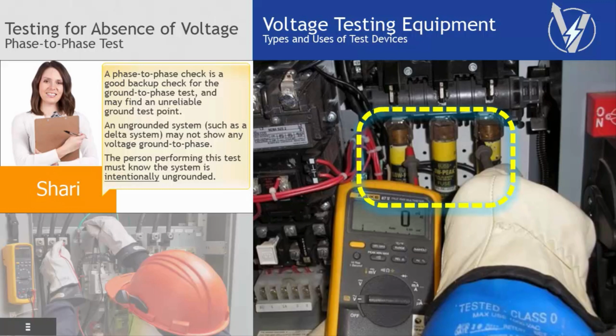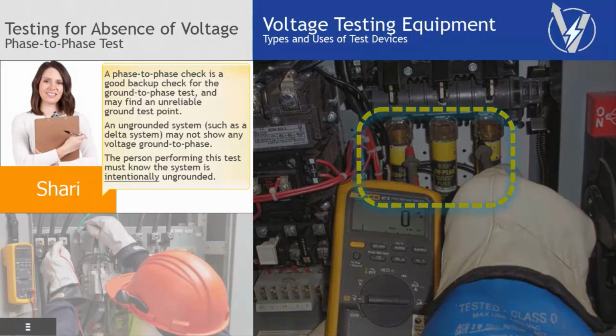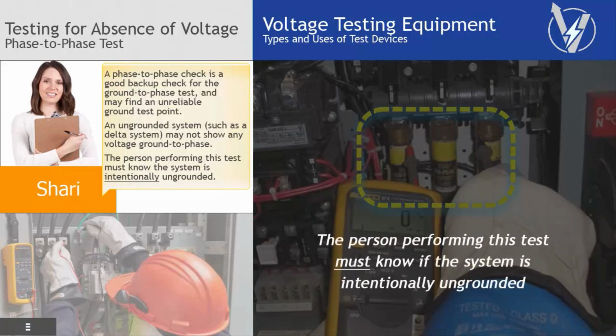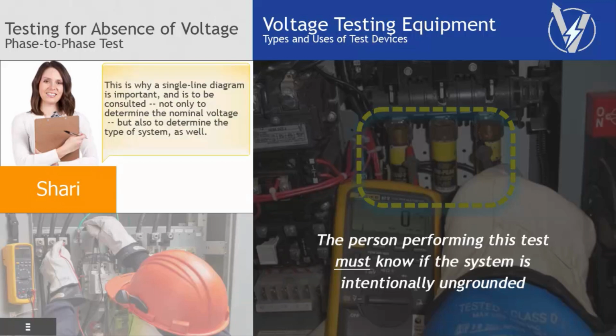An ungrounded system, such as a delta system, may not show any voltage ground to phase. The person performing this test must know the system is intentionally ungrounded. This is why a single-line diagram is important and is to be consulted not only to determine the nominal voltage, but also to determine the type of system as well.